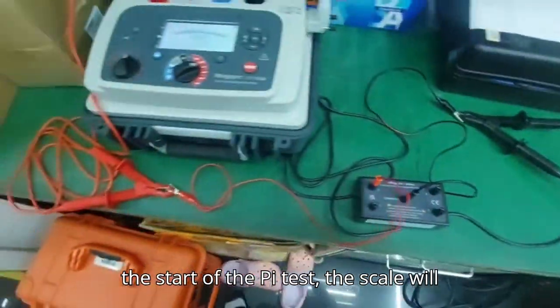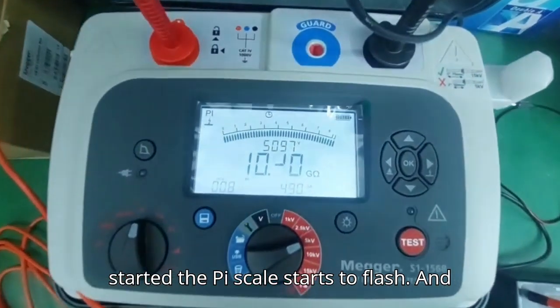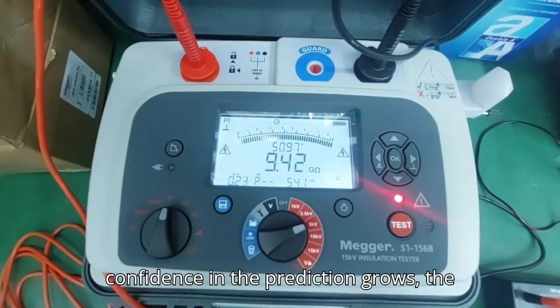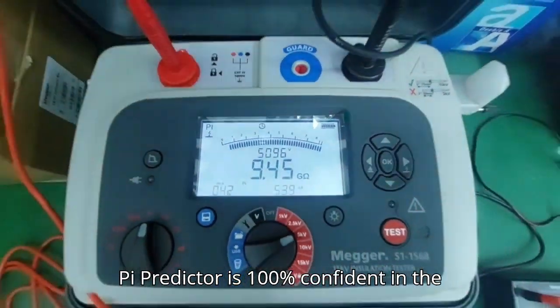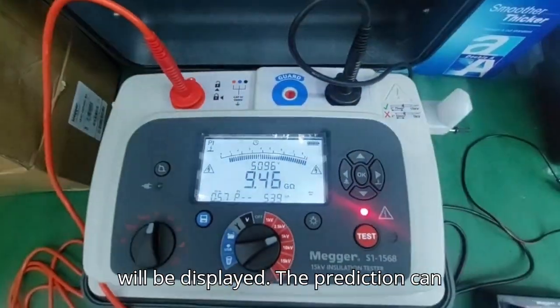During the start of the PI test, the scale will not flash. Then once the prediction has started the PI scale starts to flash. Prediction starts after 3 minutes. As the confidence in the prediction grows, the scale will become more narrow. When the PI predictor is 100% confident in the prediction, the test will end automatically and the predicted PI value will be displayed.